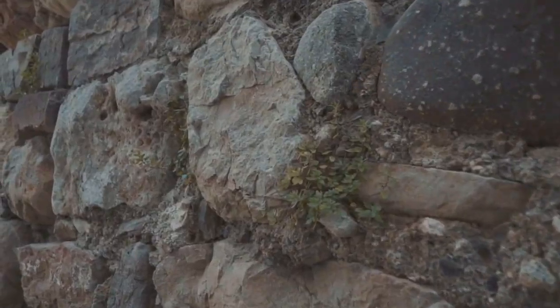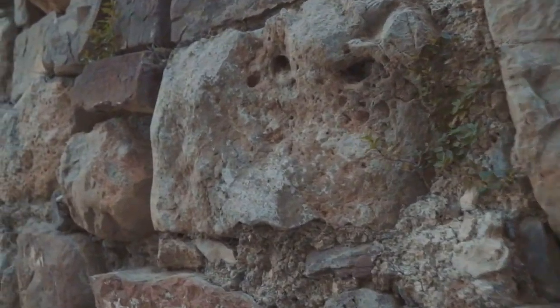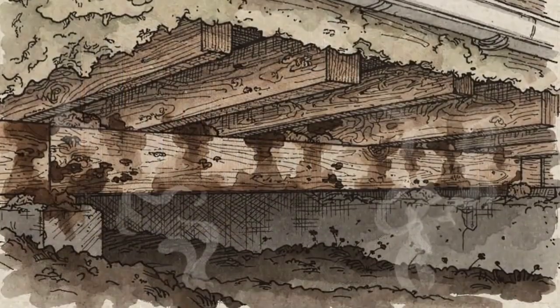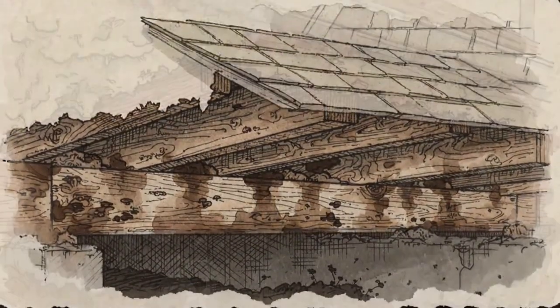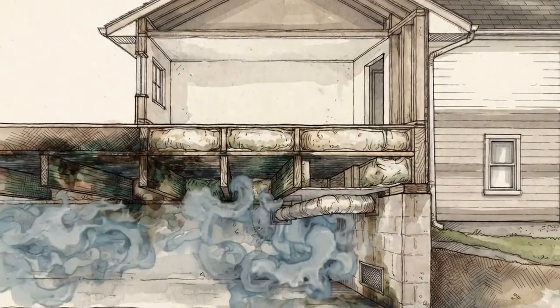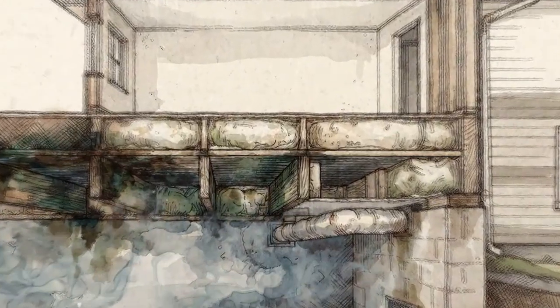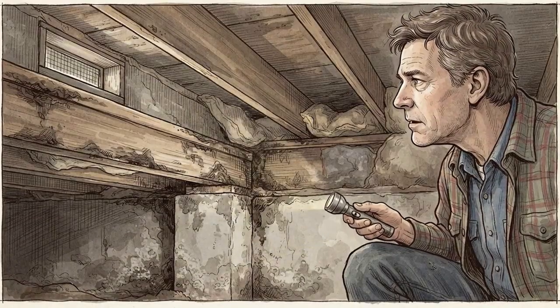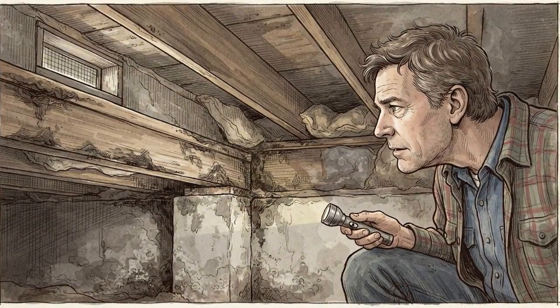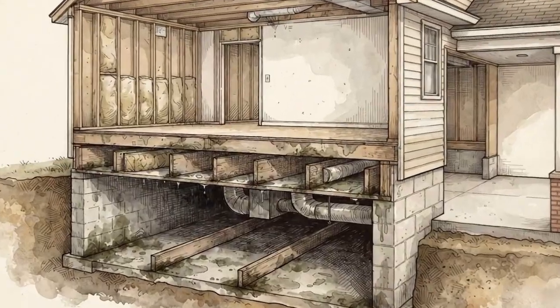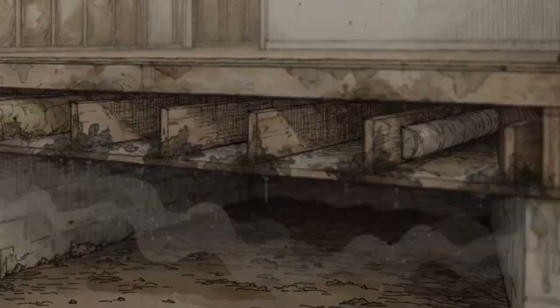You can also look for visible evidence. A flashlight dragged along foundation walls and rim joists will reveal efflorescence, the white mineral crust left behind when water evaporates off concrete, as a marker of repeated wetting. Dark staining on joist wood, especially near the ends closest to foundation walls, signals moisture before mold becomes visible.